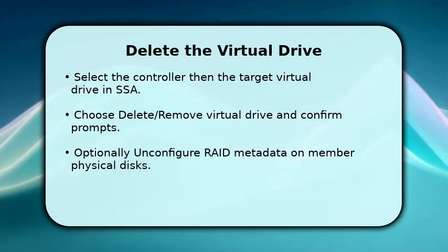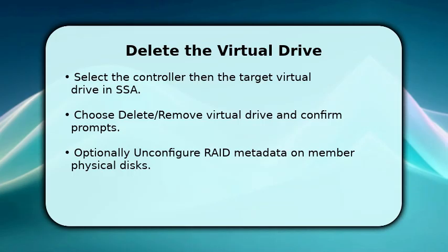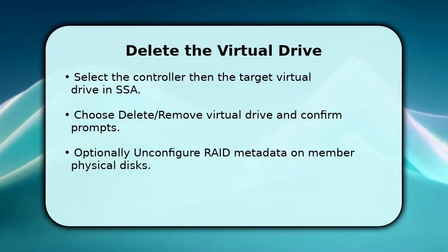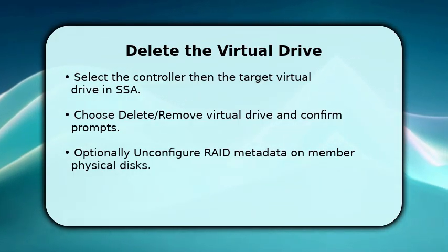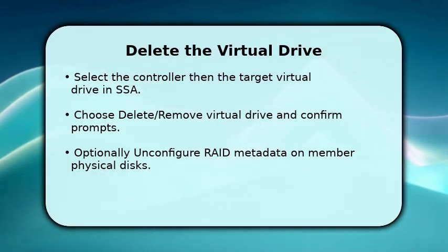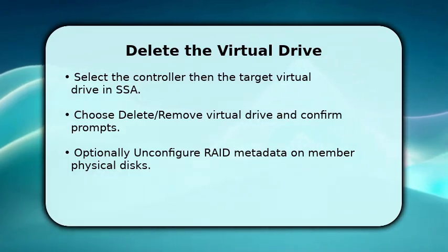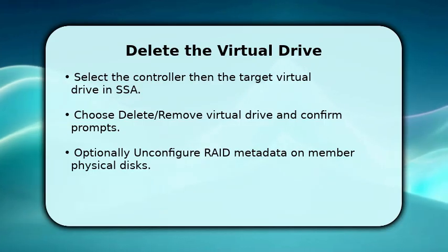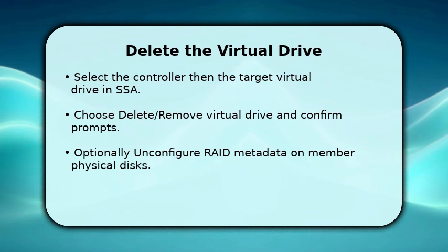If available, run the Unconfigure or Clear Configuration option on each physical disk to remove leftover metadata. Doing this ensures disks appear as raw and are safe for reuse. Make sure to watch controller logs and don't interrupt the operation to avoid inconsistent states.